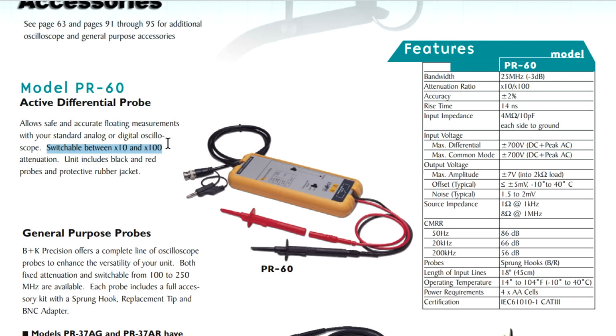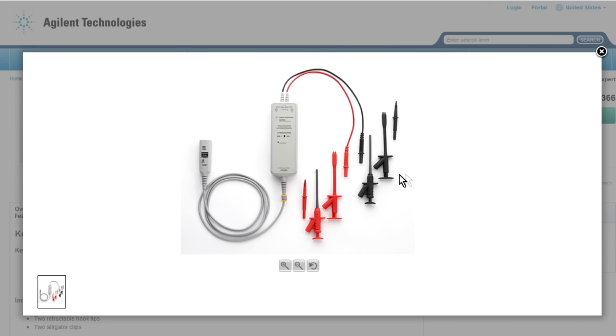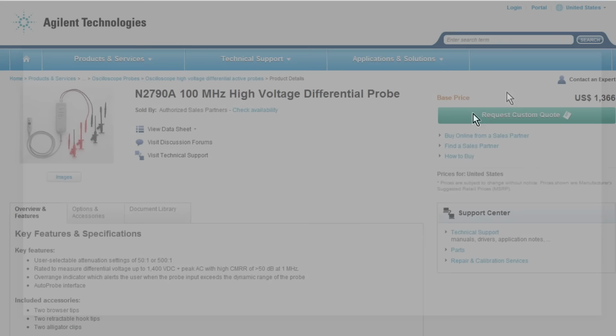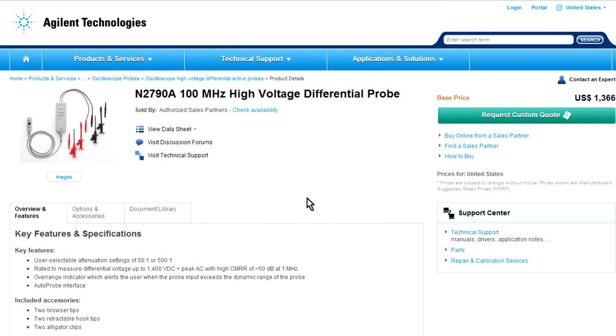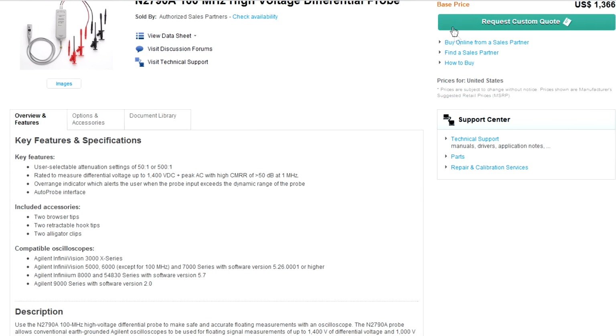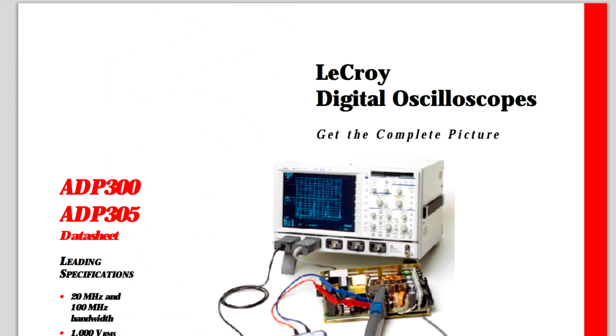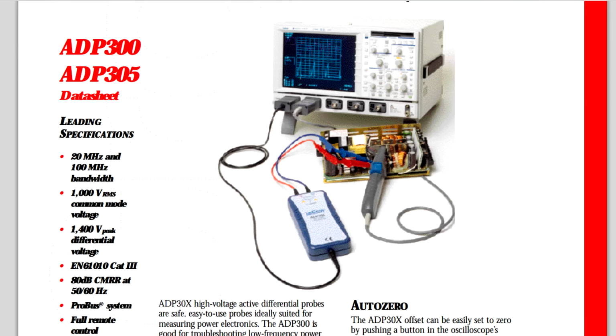But now it is differential, completely isolated, and they can be isolated to many hundreds of volts or several thousand volts. In this case, common mode plus minus 700 volts, and the differential can be plus minus 700 volts as well. And there's other ones. Here's an Agilent one, same thing, single-ended oscilloscope input through to a differential probe output. There it is. That's a 100 megahertz high voltage differential probe. And there's lots of other ones on the market. There's LeCroy, there's a whole bunch.